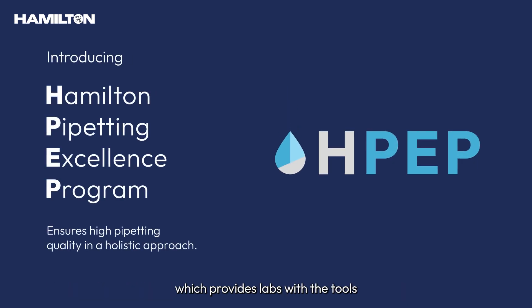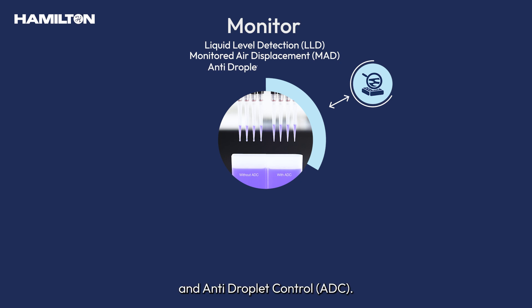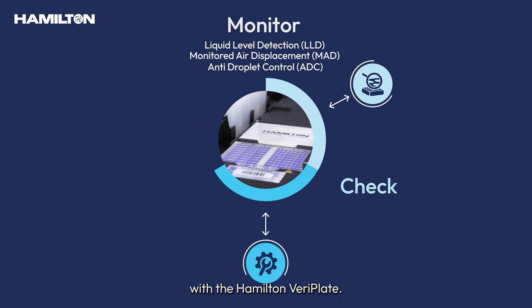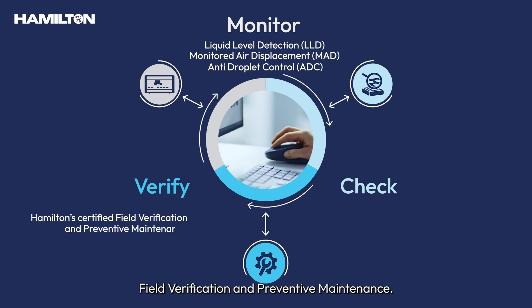The Hamilton VeriPlate is a key pillar of Hamilton's Pipetting Excellence program, which provides labs with the tools to effectively monitor, check and verify the quality of pipetting process from start to finish. Monitor: via well-known pipetting technologies such as liquid level detection, monitored air displacement, and anti-droplet control. Check: via optical image analysis of dispensed volumes with the Hamilton VeriPlate. Verify: through Hamilton Certified Field Verification and Preventive Maintenance.